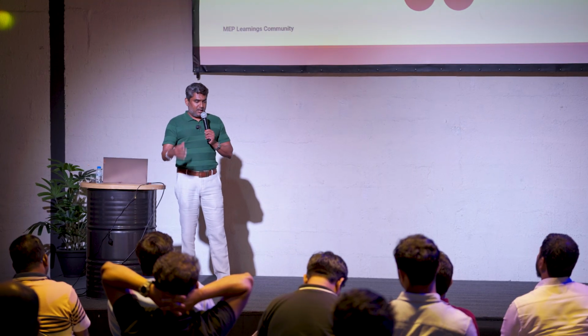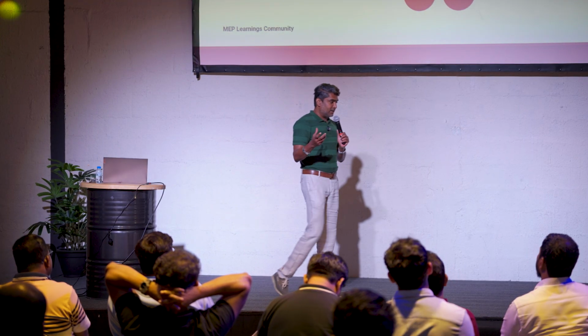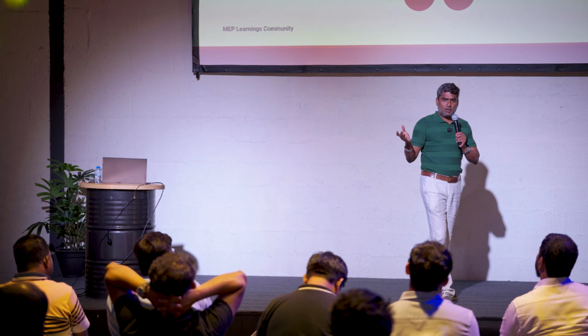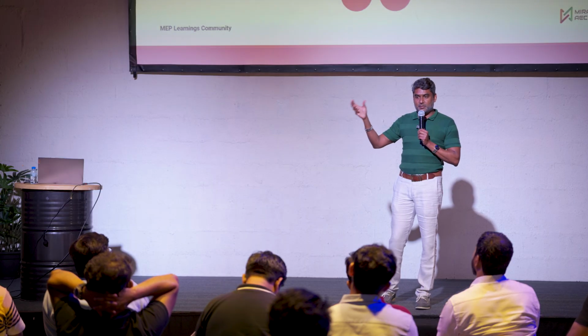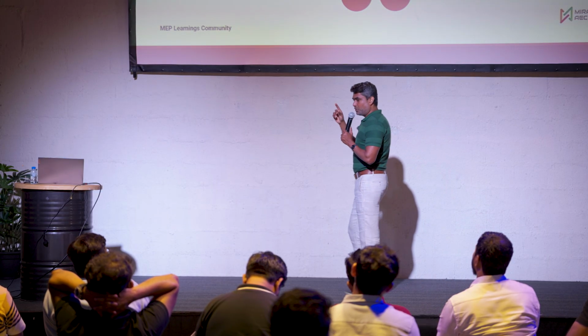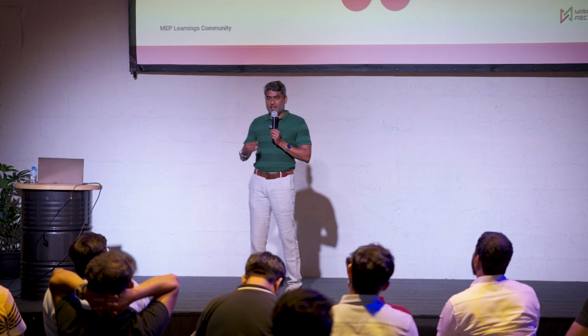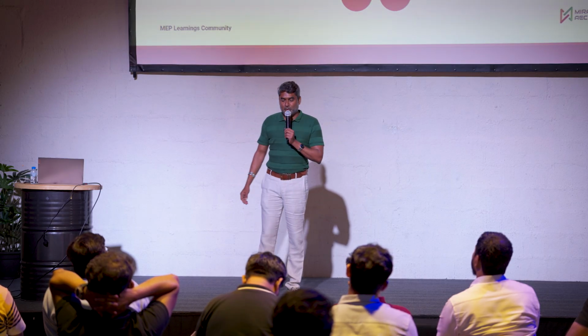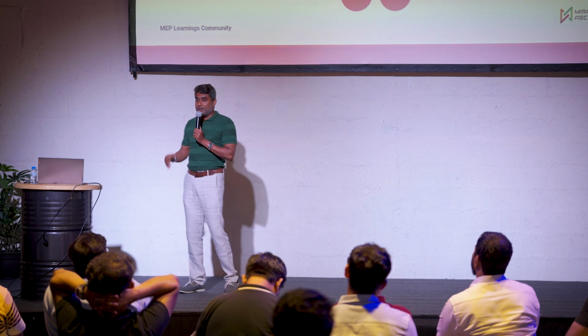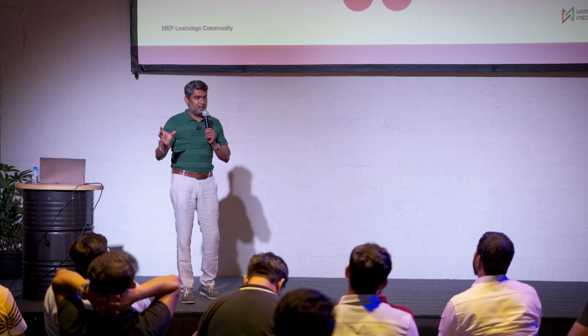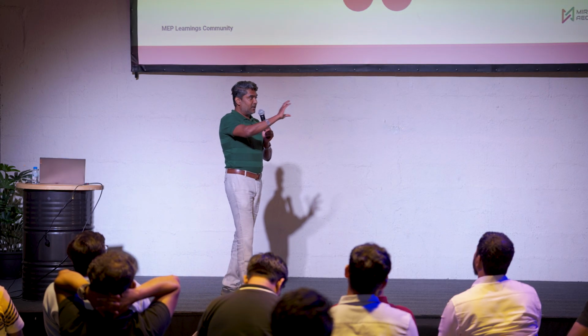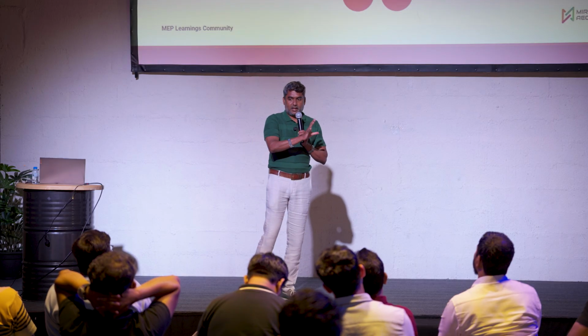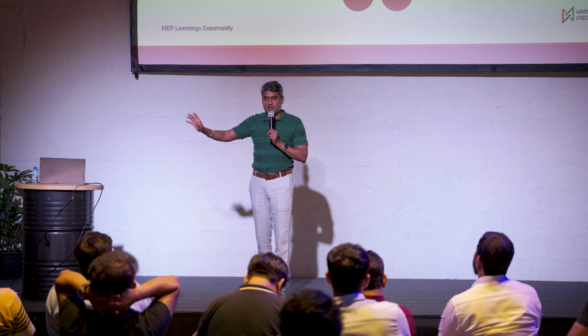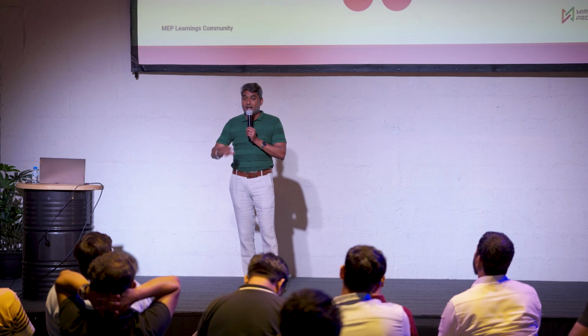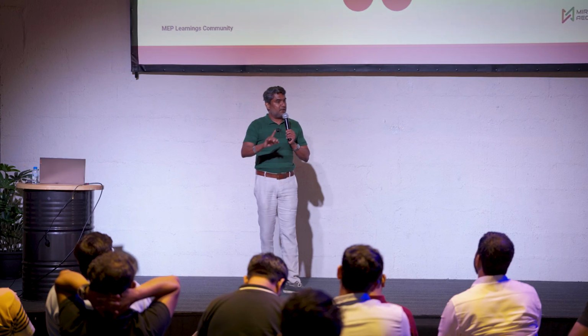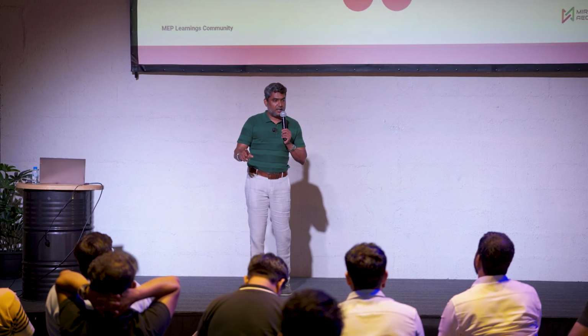Okay. The primary function, as I said in the beginning, initiating devices. So we had detectors, manual call points, IFUs, other systems through IFUs was one of the points, right? So we said flow switch in the zone control valve gives a signal. Fire suppression system, which I failed to mention then, but good that you brought it. So the fire suppression system also activates when there is a fire in the room, right? So it means that some of the area is into the fire already. So that has to be notified to the fire alarm system, so that the occupants in the building get notified and they can safely evacuate from the building.